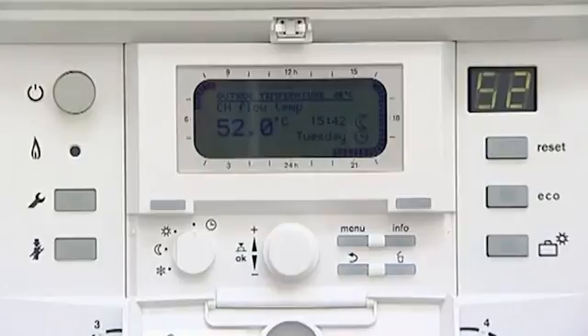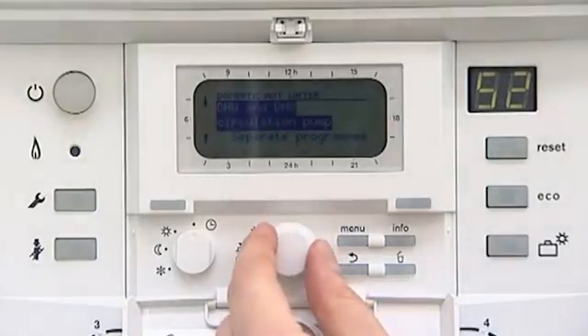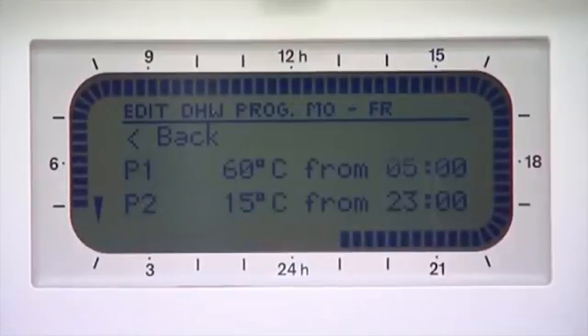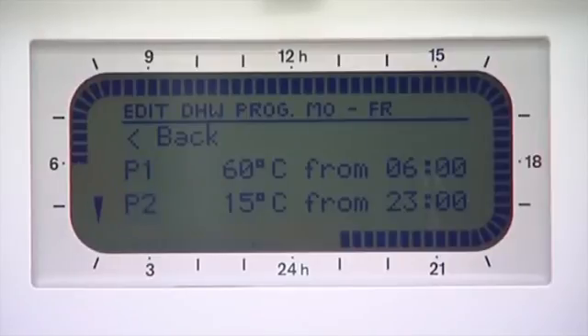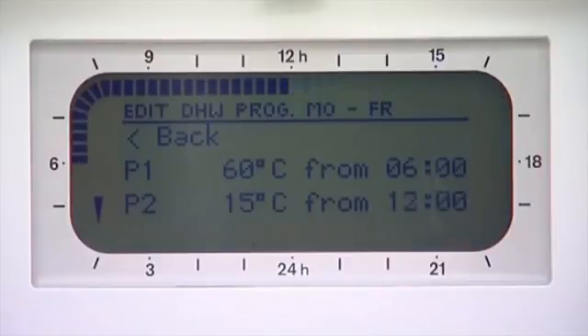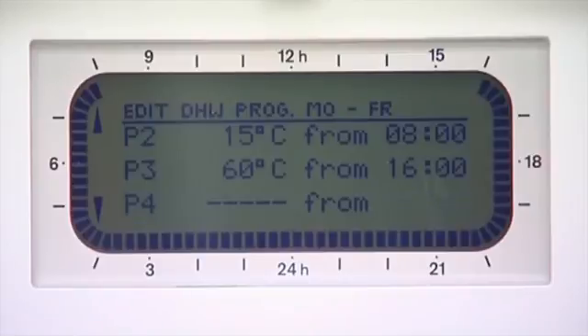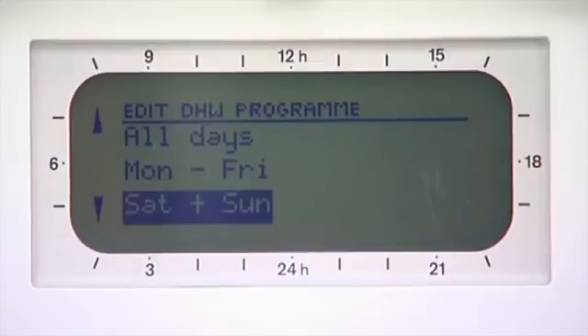Programming domestic hot water times for a system boiler with a hot water storage cylinder is very similar to that of a combination boiler. Press Menu and scroll down to the hot water. Select Edit and select Monday to Friday. Select P1 and change the times to your preferred start time and press OK. The temperature of the hot water cylinder automatically flashes its factory setting, which is set to 60 degrees Celsius. We recommend that this is not altered during an on period. Press OK. Select P2 and select the time when the hot water will be off. The factory setting is set to 15 degrees Celsius, which shouldn't be changed in an off period. Select P3 for your next on time and P4 for your next off time. Press the Back button to return to the previous menu, which will automatically save your settings. This process can also be repeated for weekends and individual days.